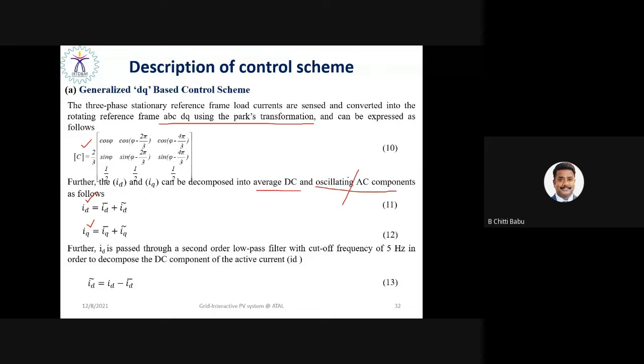This oscillating AC component must be rejected, so we use a second order low pass filter so that we take only the average DC component. ID is the direct axis component that is responsible for active power control, and IQ is the Q axis component that is responsible for reactive power control. Reactive power control is very essential to maintain the voltage profile, and active power control is very essential to maintain the frequency. So both control techniques are orthogonal to each other.